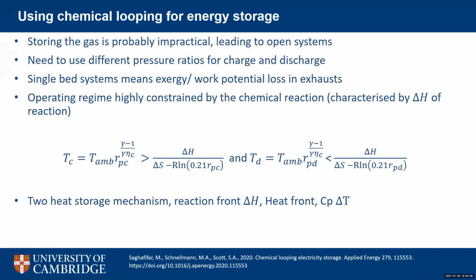The operating regime is highly constrained by the chemical reaction, which here, of course, we're characterizing by the delta H of the material. Effectively, your pressure ratio ends up being linked to the heat of reaction that you have for your material. So you can only operate at certain points on that phase diagram. And so this ends up being quite limiting when you look at how you could optimize the system. We also have 2 heat storage mechanisms. The first is a reaction front that's absorbing a large amount of heat. And also we have the heat front that you would have inside a pumped thermal storage system, where we're storing heat as sensible heat. And so you might expect that capacities might be higher than pumped thermal storage.